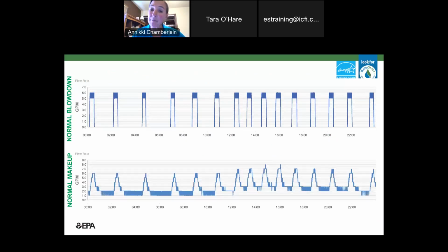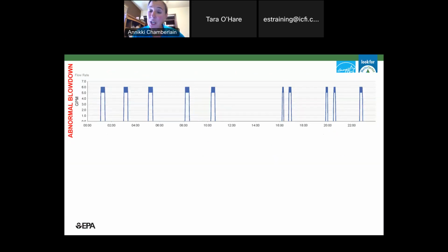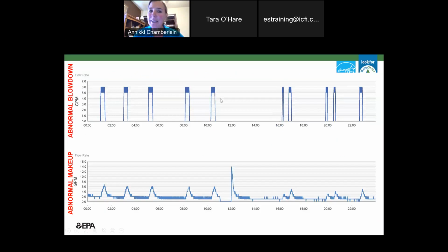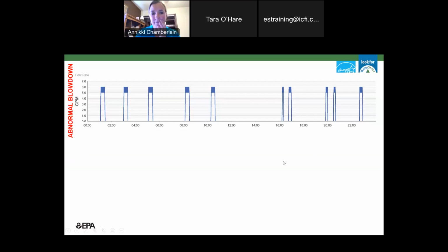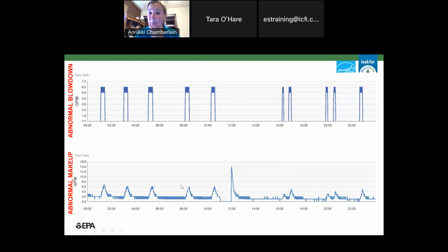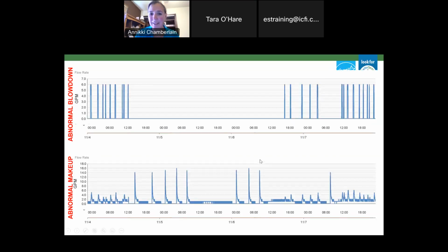We had really healthy blowdown and makeup, exactly what we want to see. All of a sudden, they made a change to the chiller setting, and we start seeing a big gap in blowdown, but also a change in the makeup. For starters, we're going to no flow, which is weird, and then a big spike. In the past, it had always been about 6 gallons per minute makeup, a little bit of constant flow. So this is definitely an anomaly. We keep our eyes on it, and we start seeing it happening a bunch. No blowdown for a couple of days, but these big spikes in use.